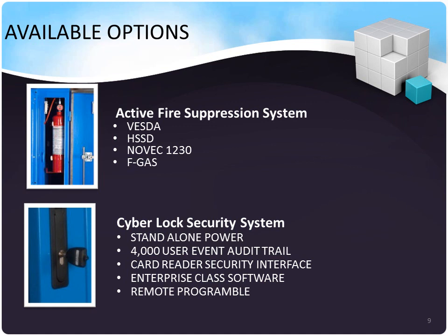Our micromodular data centers bring all of the attributes that you'd find in a brick-and-mortar data center on board. That includes highly sophisticated active fire suppression systems, including VESDA and HSSD systems using Novec 1230 or FGAS. Our CyberLock security systems use standalone power, provide an audit trail, have a card reader security interface, and can scale to enterprise-class deployments. They are also remotely programmable — another feature that comes with the unit rather than requiring a separate build-out.